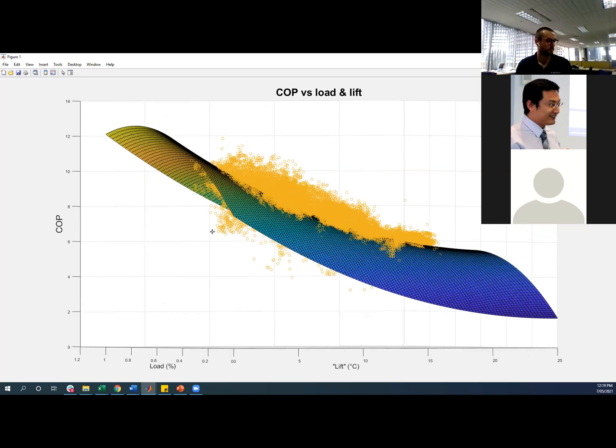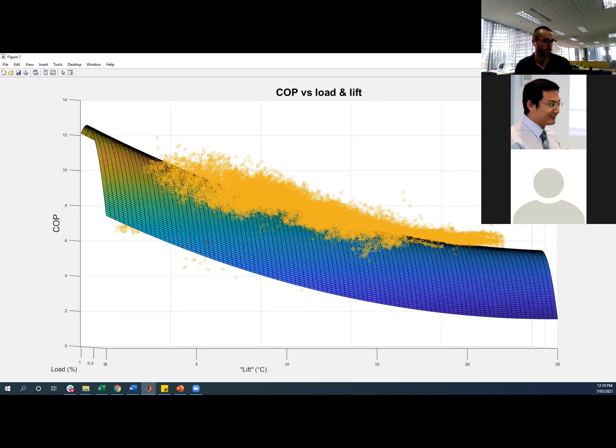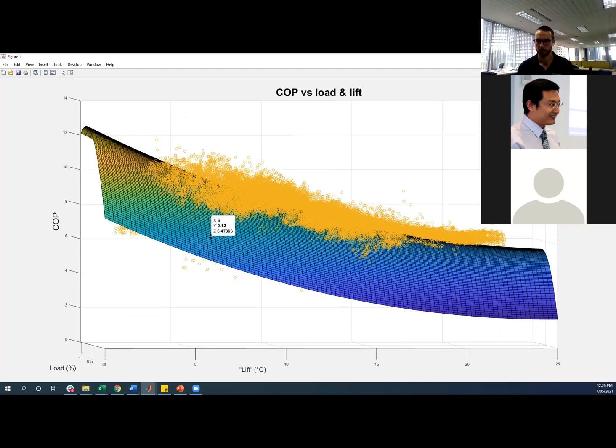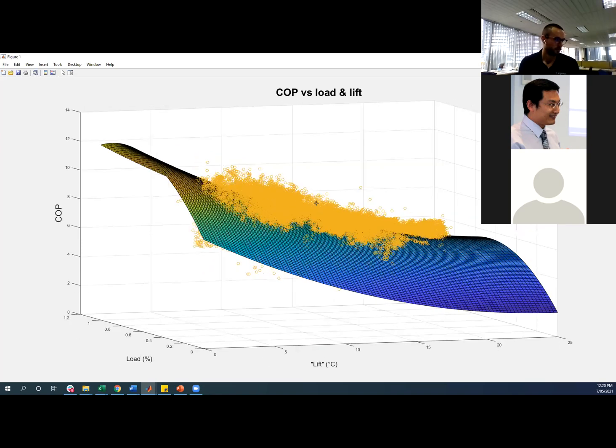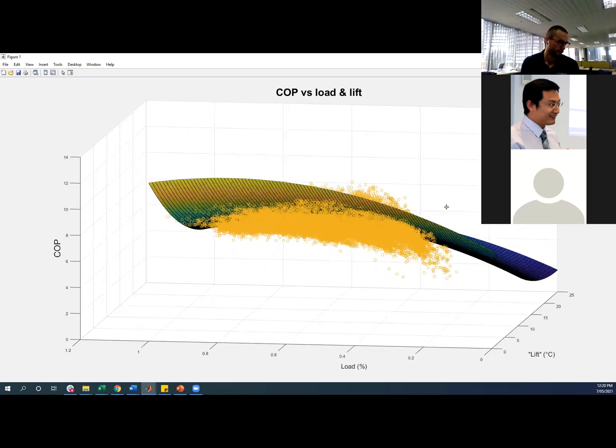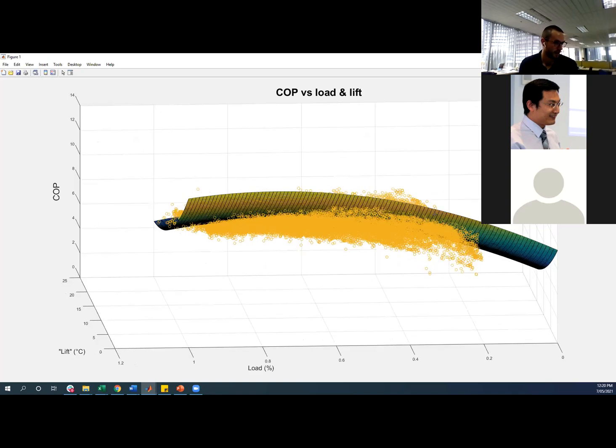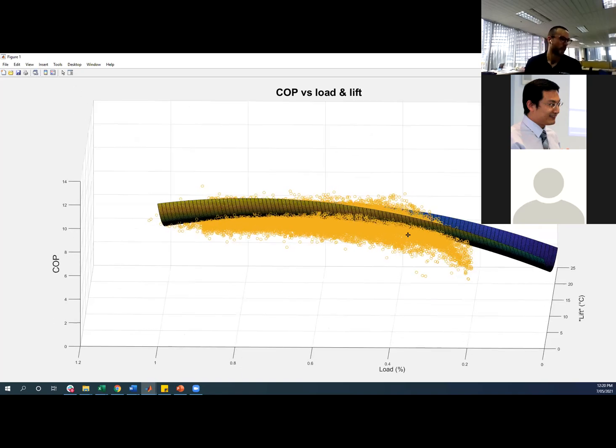But you can see here there's a pretty strong correlation even with that pseudo lift. Typically, we'd be taking the condenser water leaving temperature and calculating lift from the BMS data itself. But here we've just replaced that with weather data so that we can have something that will train our model. You can see that with these centrifugal chillers, the peak efficiency was around 80%, and they start to drop off a little bit as you get to full load.